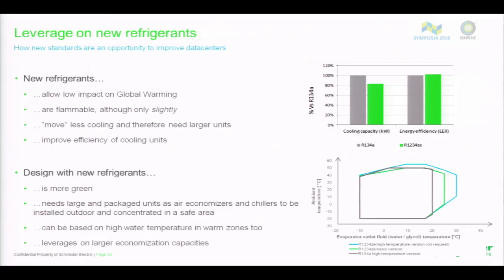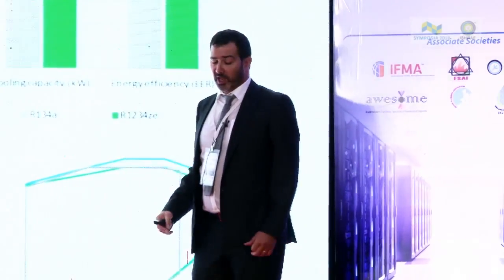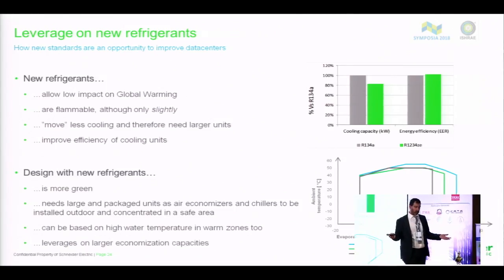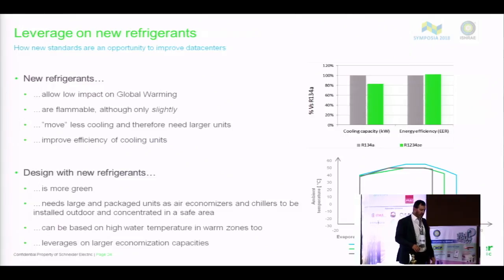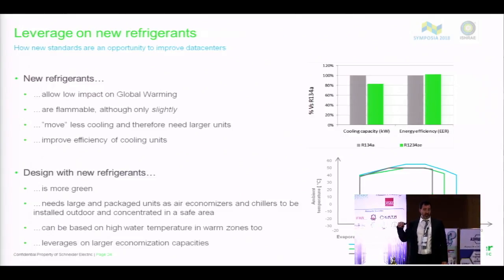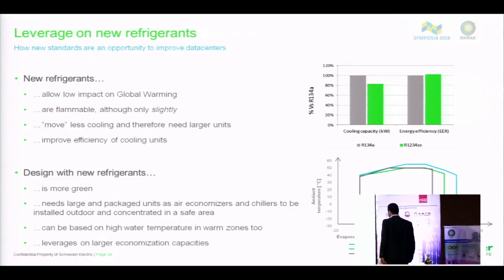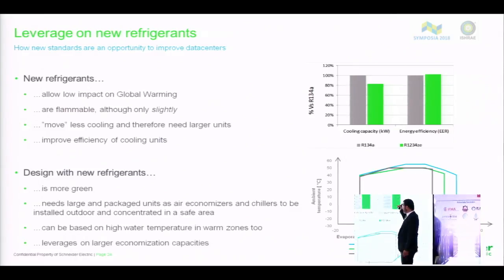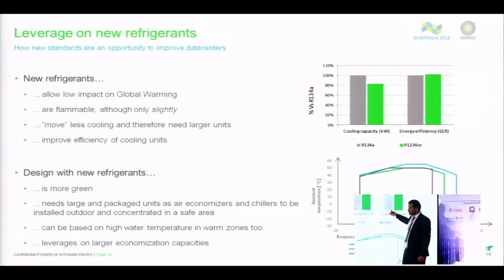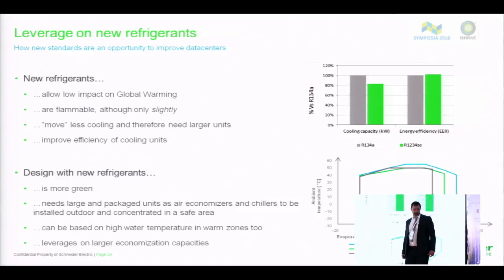So that's the refrigerant typology where we are going to land. We deployed both the ranges, of course, because it's not possible to have only one, but the 1234ZE is definitely a choice. The efficiency is slightly higher than 134A, that's good. The capacity is 20% less.